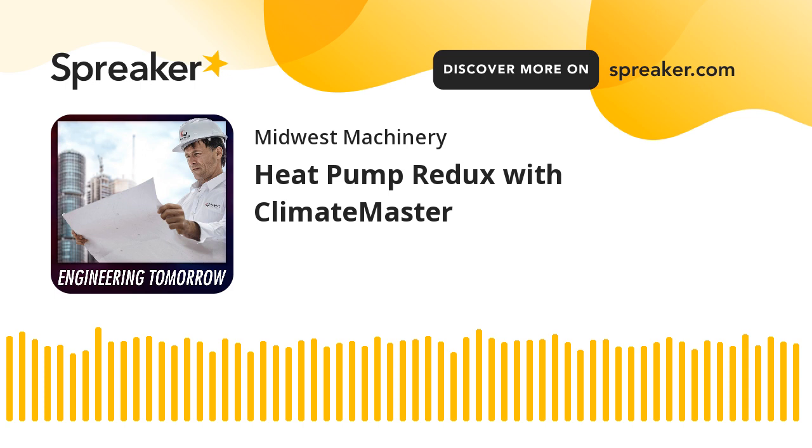One last point that I'd like to touch on before we move on is the EPA states that the average American spends 87% of their time indoors. That means quality of air is as important as the actual temperature. Designed for compliance with ASHRAE Standard 62.1, ClimateMaster offers a line of DOAS units to ensure ideal dehumidification at all ambient temps. Our systems and our controls are designed to limit space relative humidity to 60% or less during all load conditions. The reason I bring this up is, if you're familiar with water source heat pumps, we need some form of ventilation system. One of the ways to accomplish this is with a dedicated DOAS system.